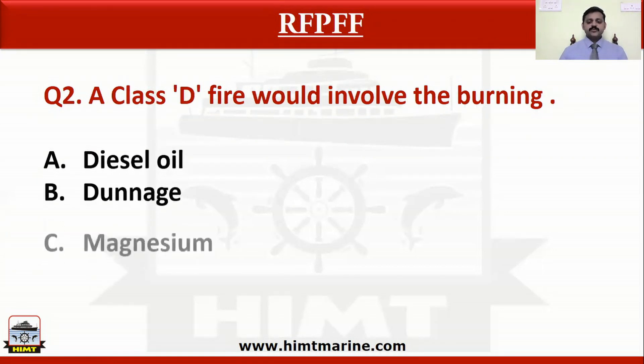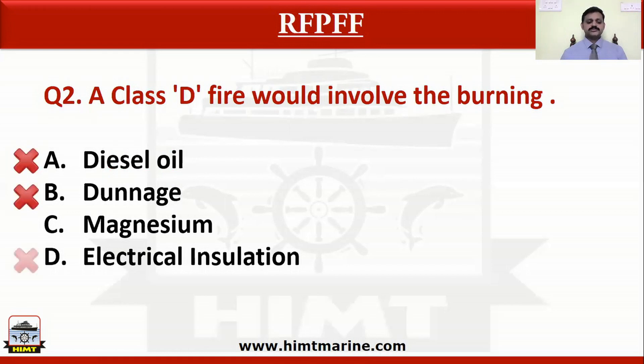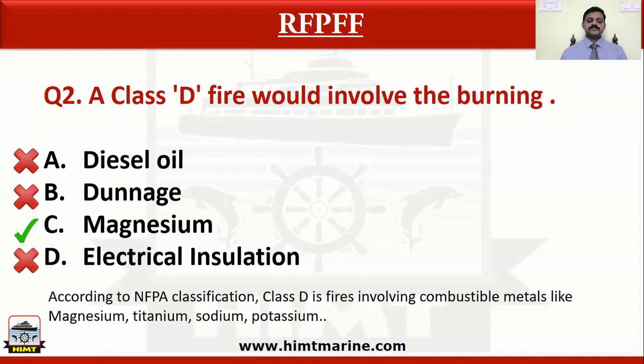A class D fire would involve the burning of: option A diesel oil, option B dunnage, option C magnesium, option D electrical insulation. The correct answer is option C magnesium, because according to NFPA classification, class D is fire involving combustible metals like magnesium, titanium, sodium, potassium, and zirconium.